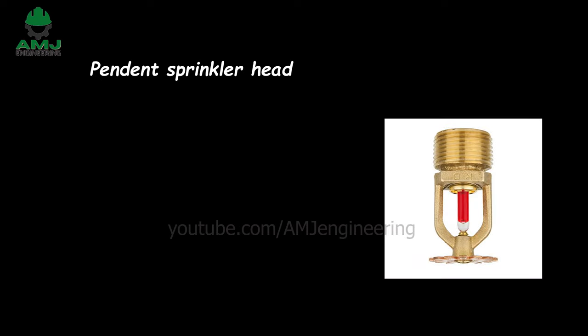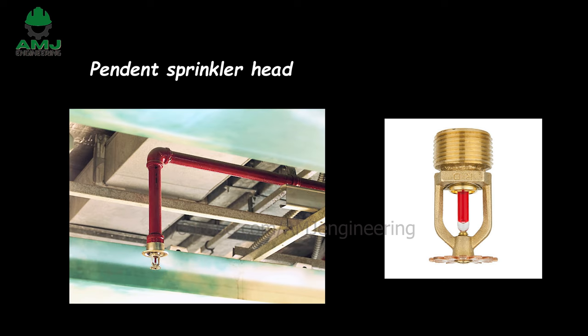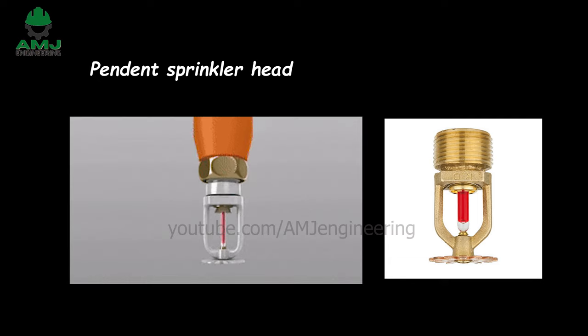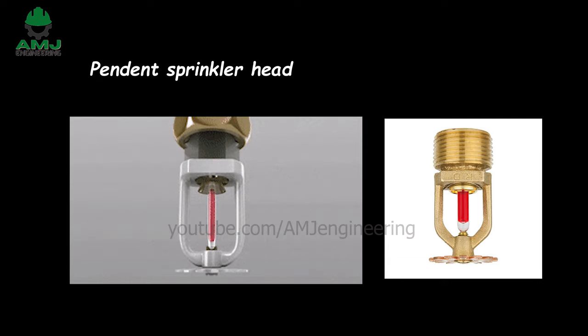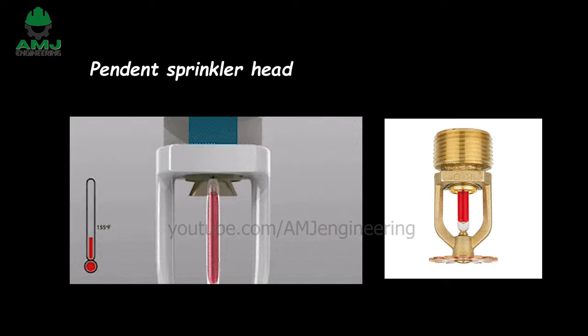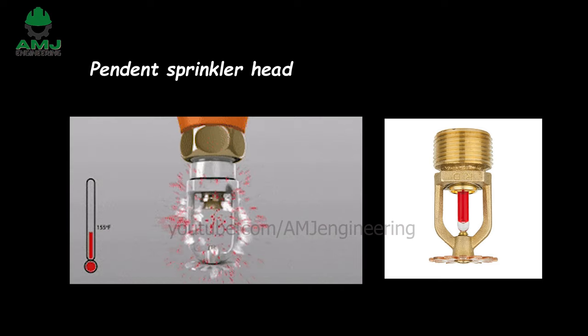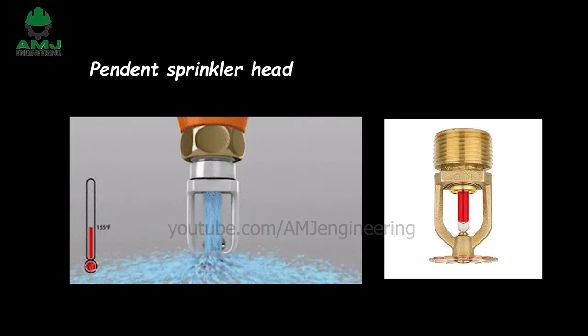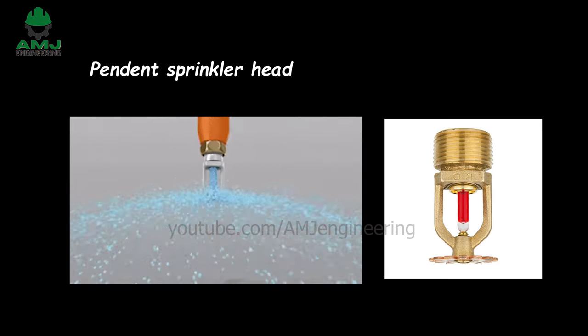The pendant fire sprinkler head is the most common type that you will see. Pendant sprinkler heads descend from the ceiling with a convex, circular, cap deflector plate on the bottom. When the sprinkler heads activate, they send a stream of water downward onto their deflectors, which then disperse the water widely, side to side, throughout the room in a conical pattern.